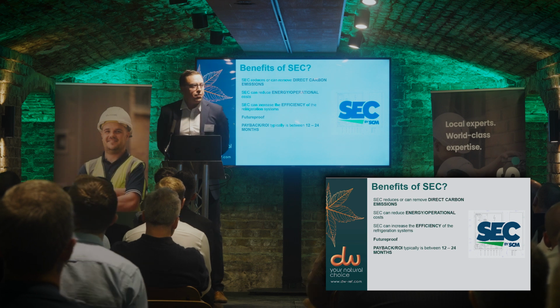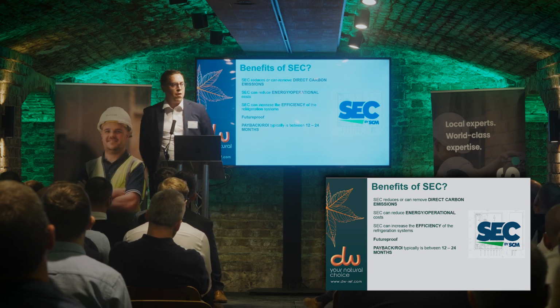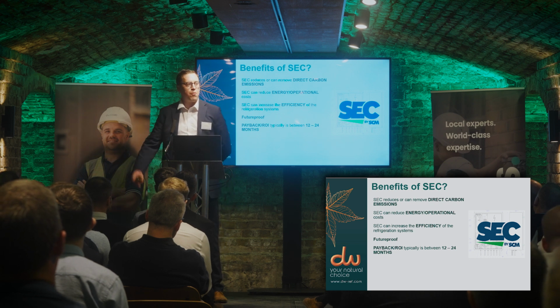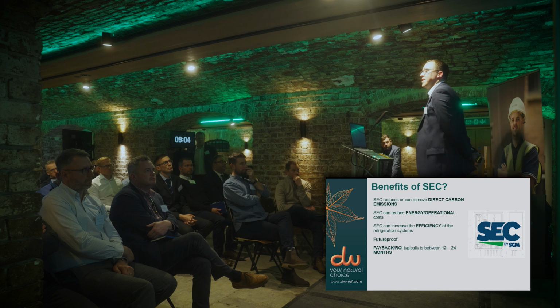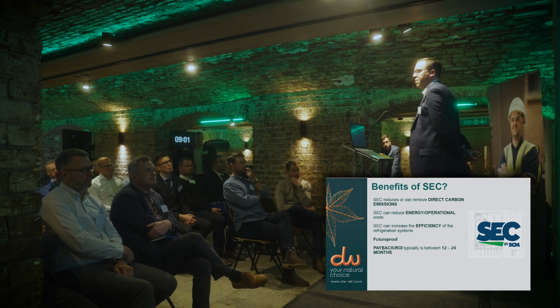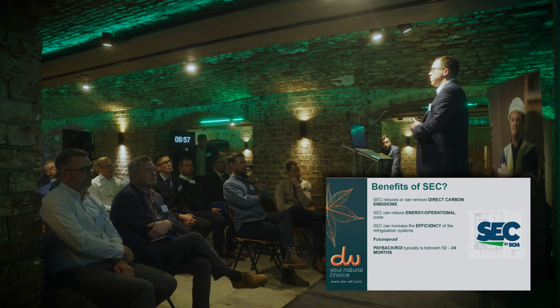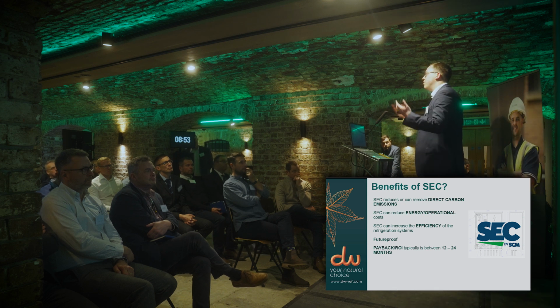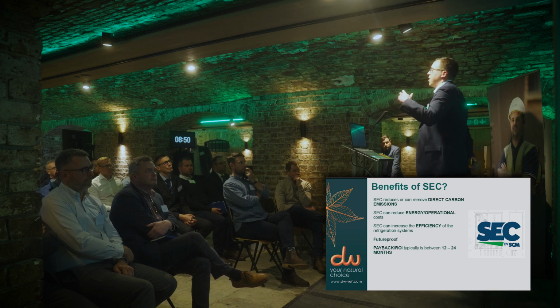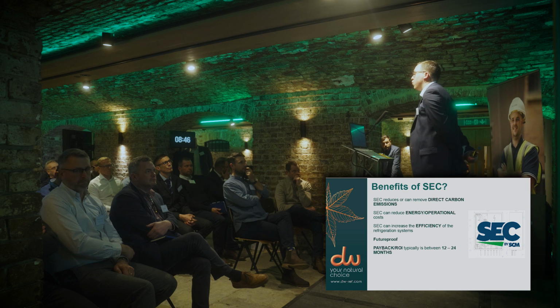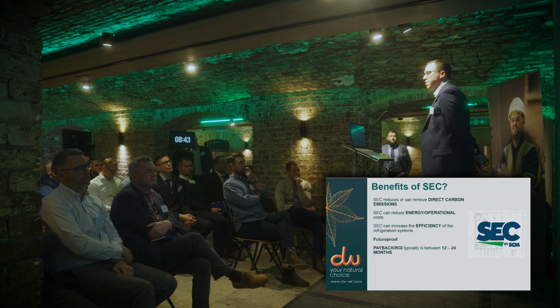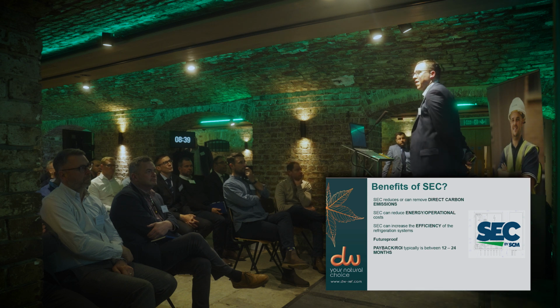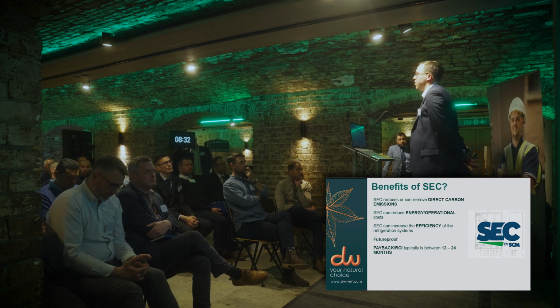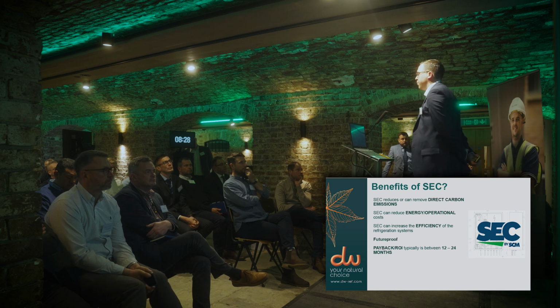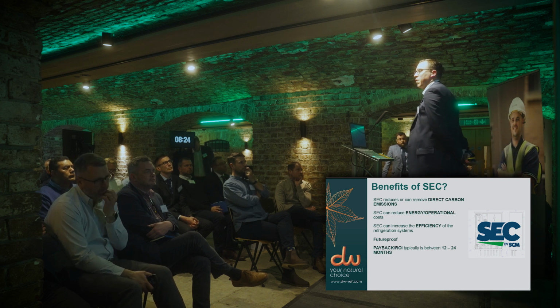What are the benefits? So we can remove direct carbon emissions related to the generation of hot water. We can reduce the energy and the operational costs related to generating hot water. We can improve the efficiency, and this is probably a softer benefit of the SEC panel, but if you've got systems that struggle in high ambience, certainly in London where you've got things located internally, by us removing the heat, that will help the overall cooling performance of that system. It's a future-proof technology, and typical paybacks, which is a really important factor in all of this, we see for electric generation of heat is probably 12 to 18 months. If you've got a gas boiler, then typically it's between 12 and 24 months. So really quick payback on your investment.